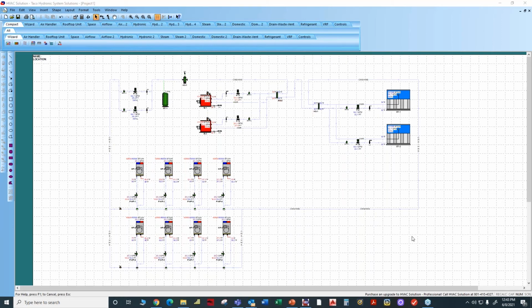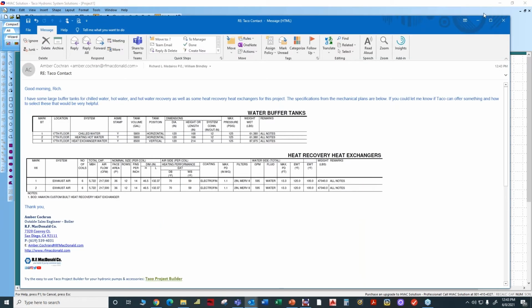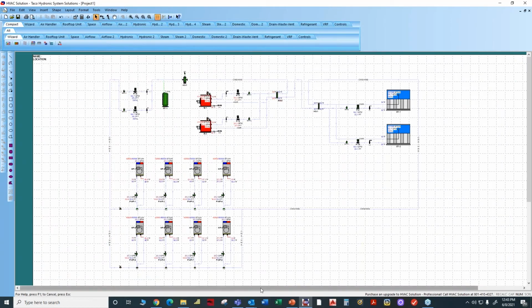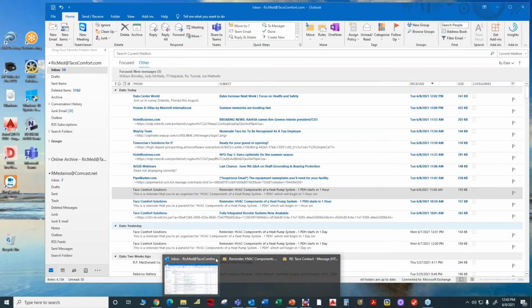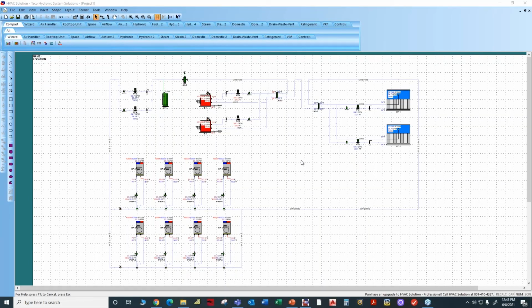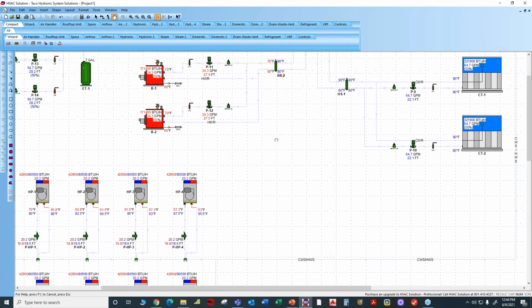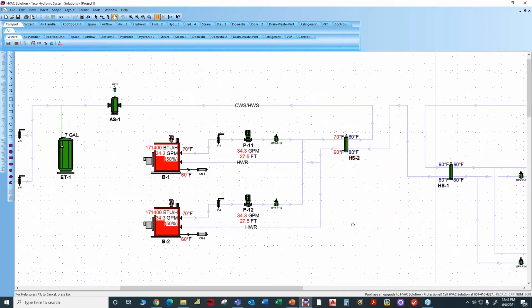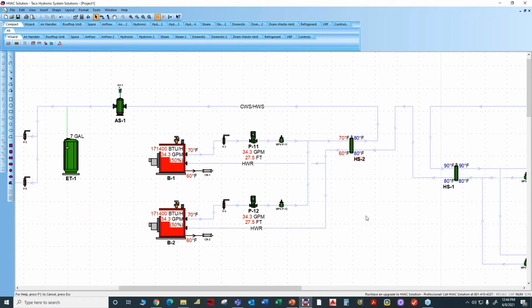And in the water source heat pump system, let me, sorry about that. Let me shut off my email. If I don't do that, I'll get some. So let's look at the primary secondary loop. Zoom in here a little bit on the heating side. So in this particular case, the water temperature being generated by the boiler is around 70 degrees Fahrenheit, and that 70 degrees Fahrenheit is trying to heat up that water through the primary secondary loop.